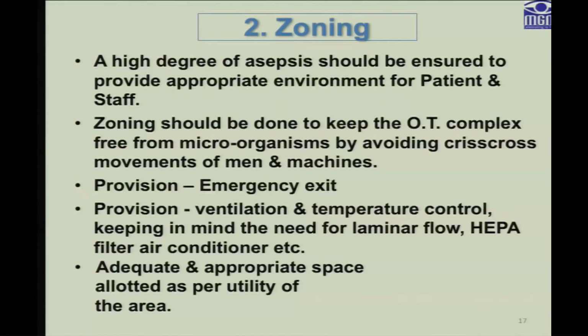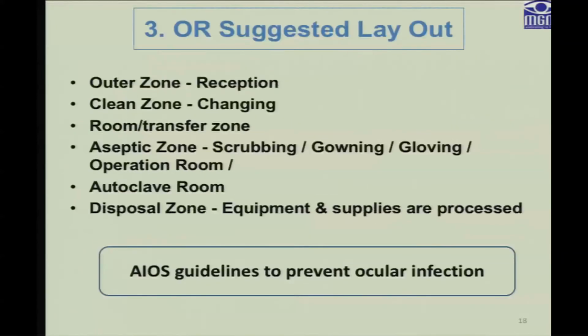Next comes zoning. A high degree of asepsis should be ensured to provide an appropriate environment for patients and staff. Zoning should keep the OT complex free from microorganisms by avoiding crisscross movement of men and machines. There must be provisions for emergency exits, ventilation, and temperature control, keeping in mind the need for laminar flow, HEPA filters, air conditioning, etc. Adequate and appropriate space should be allotted as per the utility of the area.